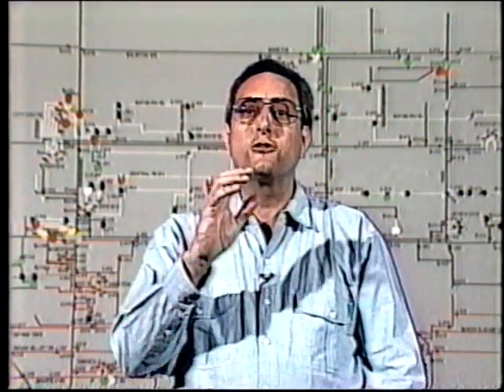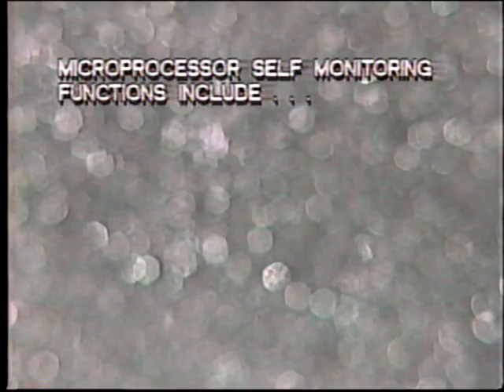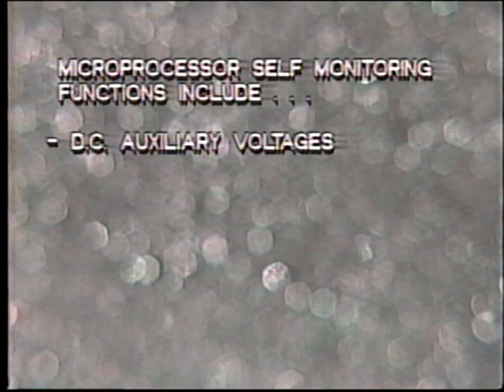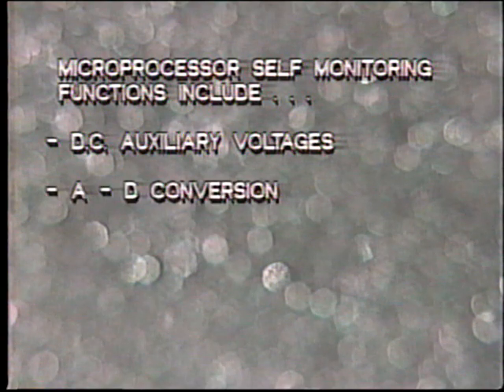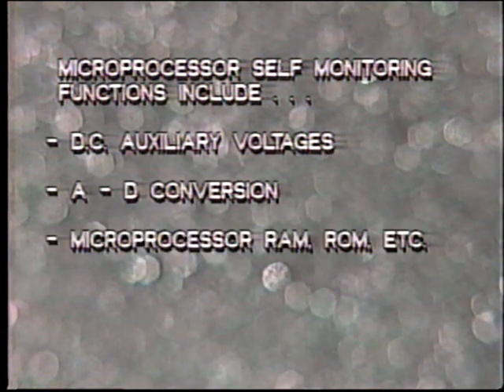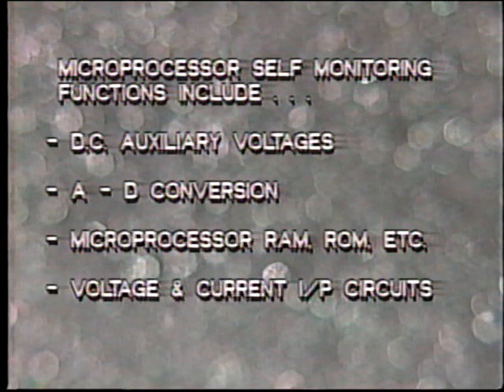Another advantage of the microprocessor relay is the ability for self-monitoring and self-testing at frequent intervals. Any hardware failures are immediately alarmed or reported over the substation control system. The self-monitoring functions typically include DC auxiliary voltages, A to D conversion, microprocessor RAM, ROM, etc., voltage and current input circuits.